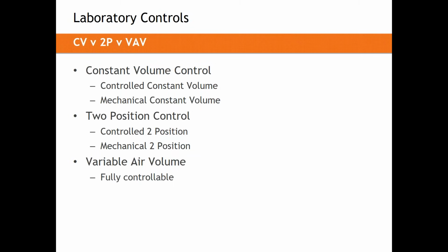Now, the reason we recommend that is it's lower cost than a VAV box. Number one, the capital cost is lower, but number two, the maintenance cost is lower because there's no parts that are moving, there's no controls, electronics, or motors of any kind. It's just mechanically fastened into place. So this is where, for you engineers that are speccing Venturi valves and scheduling valves, it's important to note the difference. We see a lot of schedules that call out constant volume airflows on Venturi valves, but what they would like to see is a controlled constant volume.